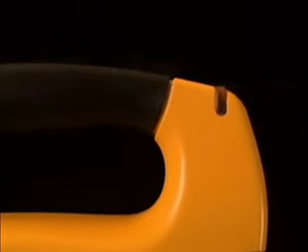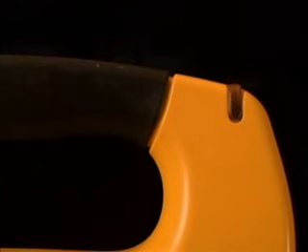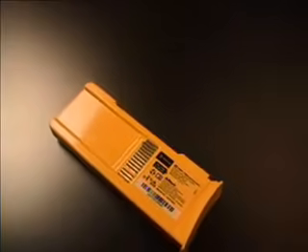The active status indicator, also known as the ASI, is located in the upper right corner of the AED and flashes periodically to indicate the status of the Lifeline. A flashing green ASI indicates the Lifeline is ready to perform a rescue. A flashing red ASI, or no ASI at all, indicates that the device may not be ready to perform a rescue and may need additional attention. The ASI is powered by a 9-volt battery located in the battery pack.